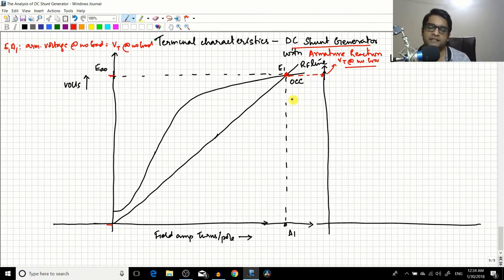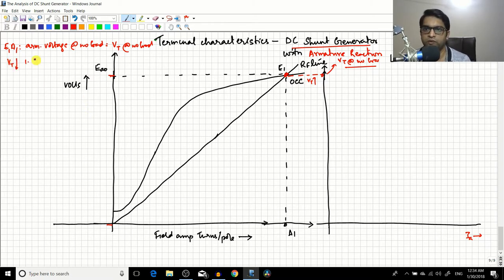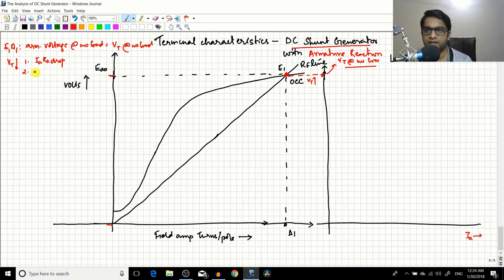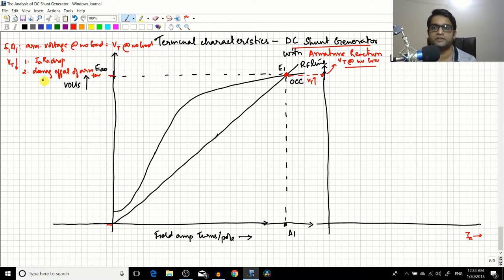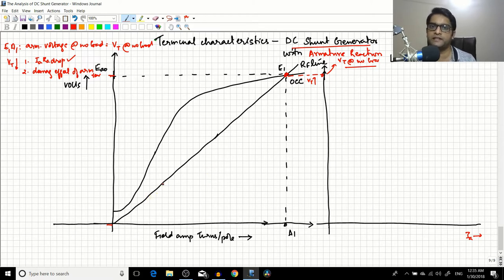As Ia increases, Vt will decrease. The decrease of Vt is due to two reasons. First is the IaRa drop, which we have already considered in previous lectures. The second reason is the demagnetizing effect of the armature reaction. We have to consider this effect because the demagnetizing effect actually reduces the internally generated EMF Ea itself. Since Vt equals Ea minus IaRa, if Ea decreases then Vt also decreases. That is what we are going to consider in this session.